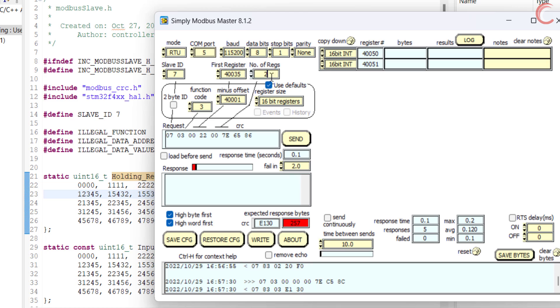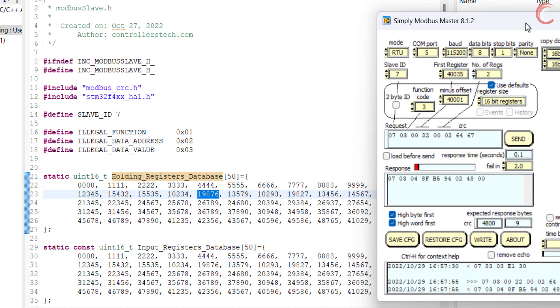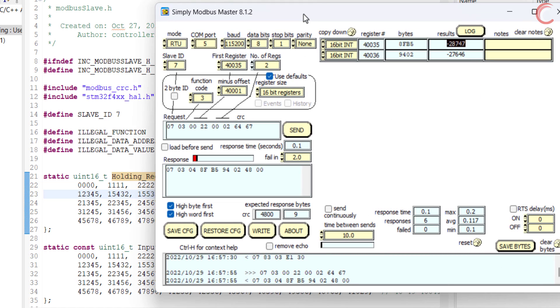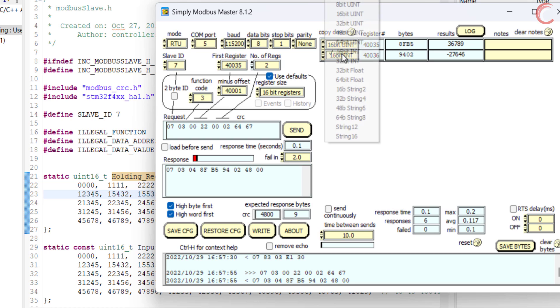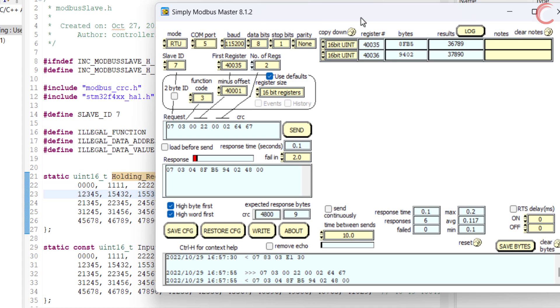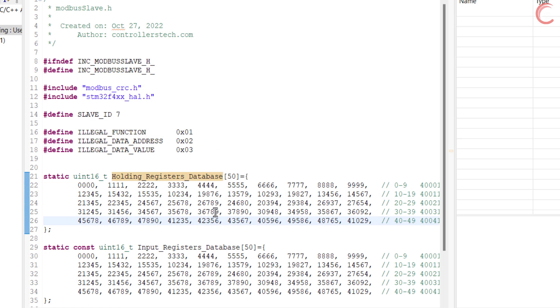There is one more thing I want to point out. Let's say the master wants to read two registers starting from 40035. Here you can see the negative values in the respective addresses — this is because the data type is set as a 16-bit signed integer. Let's change this to 16-bit unsigned integer. Now you can see the positive values, and they are the same as what we stored in the database.